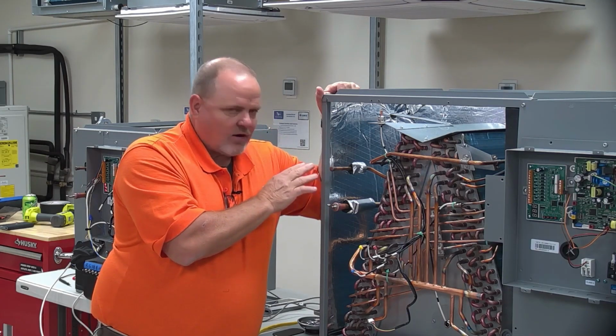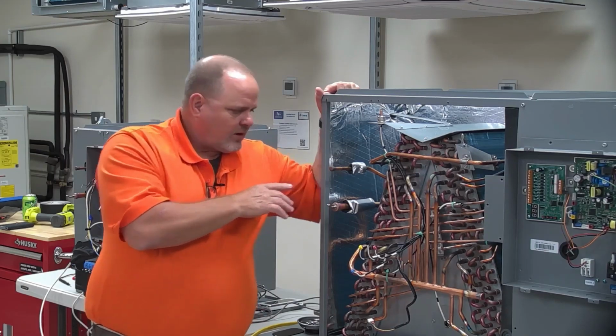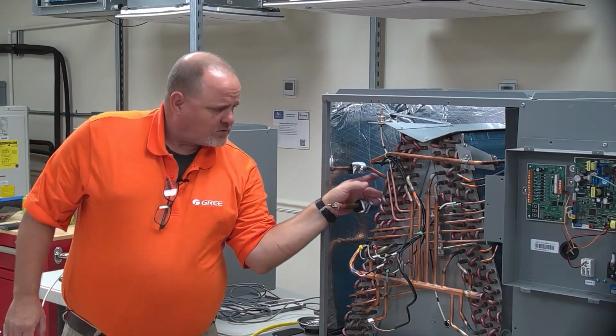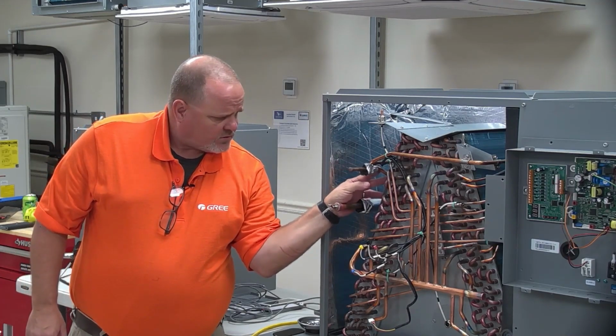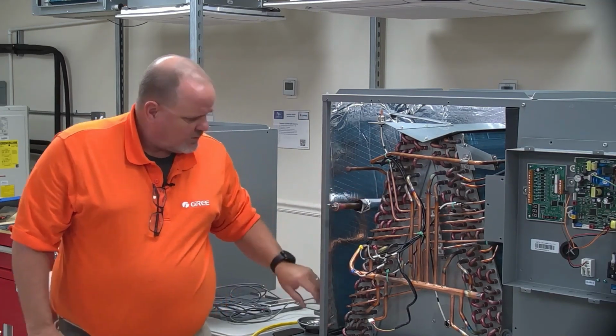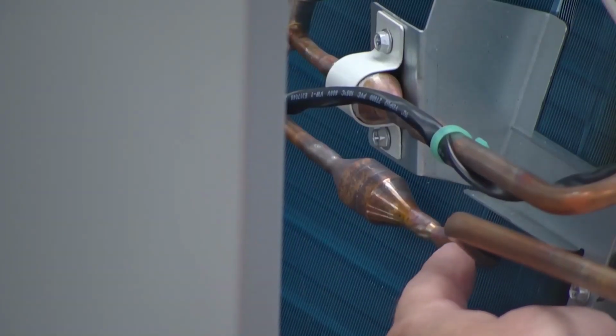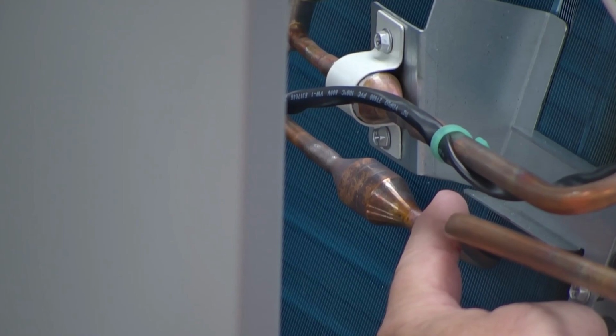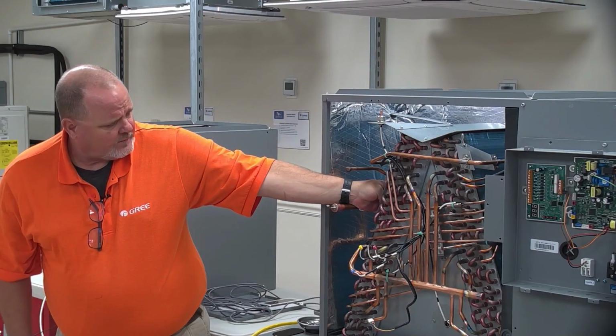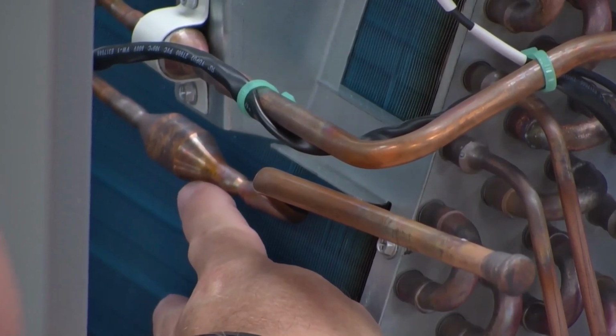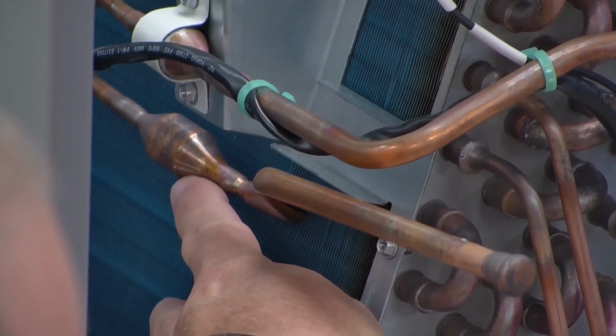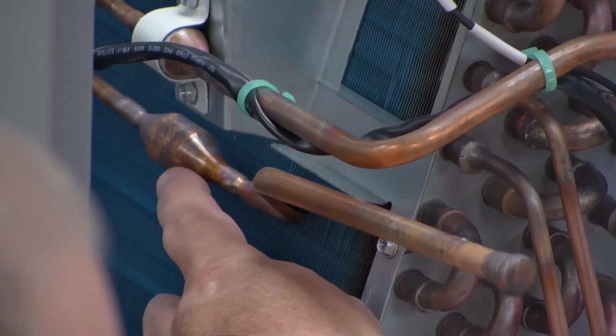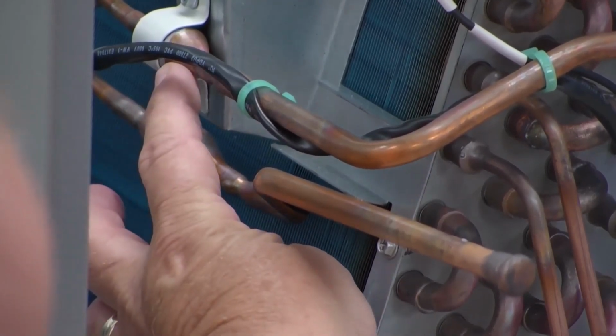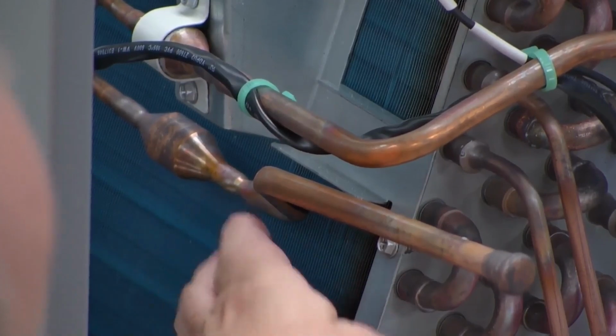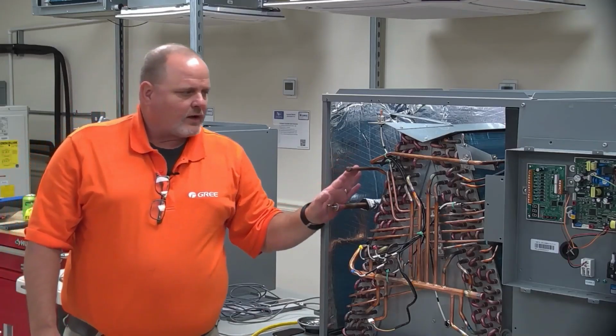But I will say, and it's kind of hard to see, I think we can probably get the camera zoomed in here to take a look. Kind of push that over to the side a little bit. Let me pull this off. I do want to point these out. There's one here and there's one up there. So those are inline strainers. We want to be really careful and make sure that we're flowing nitrogen when we're brazing, because we don't want to plug up those strainers. So you've got one on the inlet going into the EEV and one leaving the EEV. So make sure you're flowing nitrogen when you're brazing on this thing on both lines.